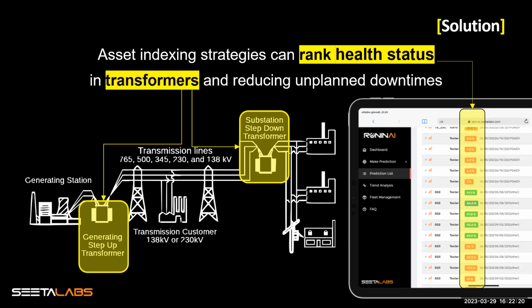With the advent of online sensors, you can imagine the huge influx of data generation right now. Typical online DGA sensors generate 4 readings in one day. So you can imagine the amount of data generated for one transformer in one year, and if you have a fleet of 500 or 1000 transformers, you can multiply that.